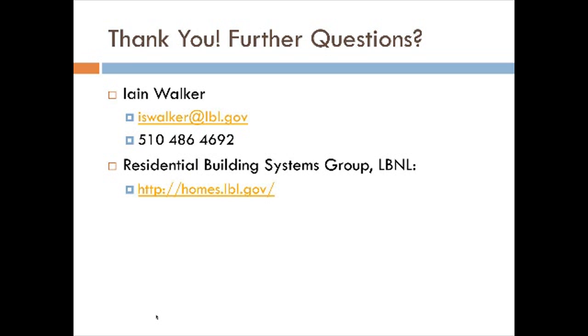Okay, the next question: is there an industry standard ASTM blower door test method for multifamily homes? Oh, that's a good loaded question. Well, most of you on the call are probably familiar with ASTM E779, which is really applied for single family only. And there are various protocols out there that various institutions have put together. There is no ASTM or ISO standardized test method that deals with multifamily.